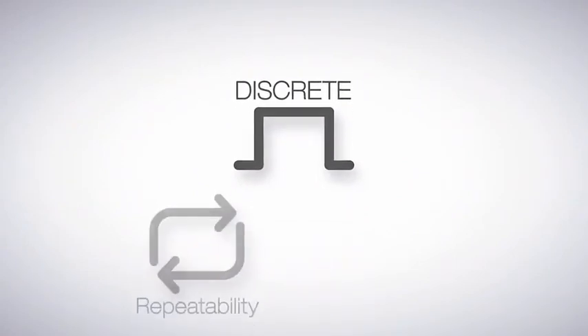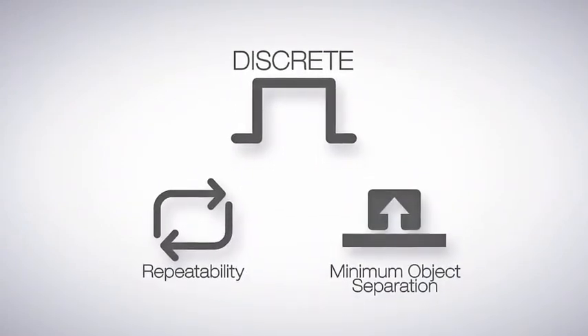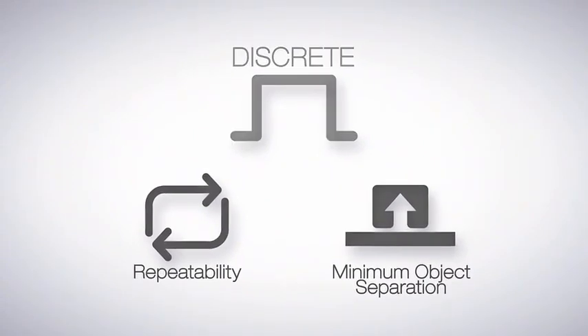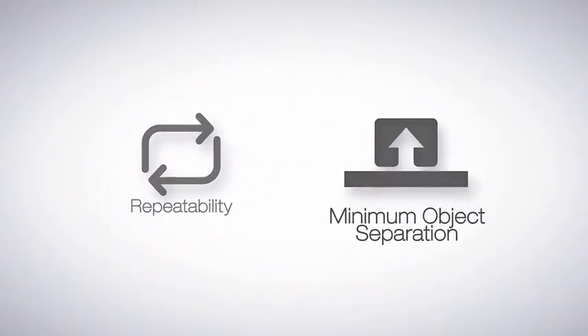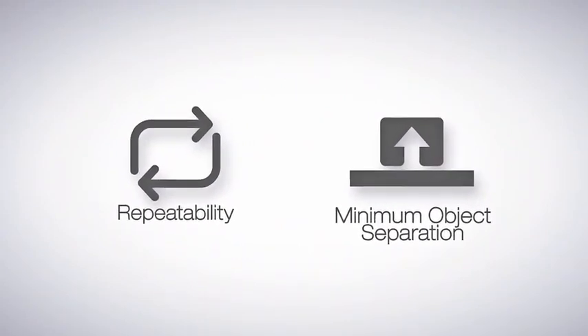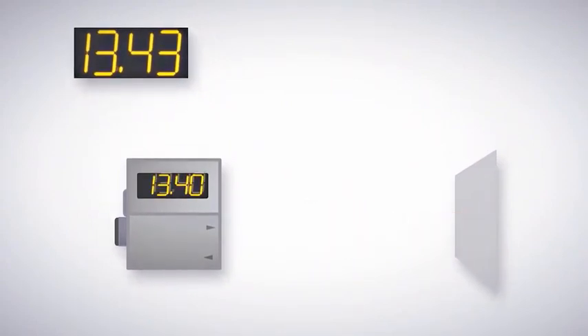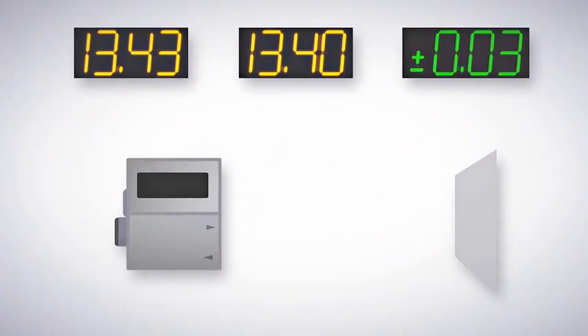In discrete applications, repeatability and minimum object separation are two specifications used to describe sensor capabilities, but not all specifications are equal indicators of real-world performance. Repeatability is the measurement of how reliably a sensor can repeat the same measurement in the same conditions. It is calculated by having a sensor detect a motionless, single-color target multiple times in a laboratory setting. For that reason, repeatability is a useful specification for comparing products, but it is not the best indicator of real-world performance.